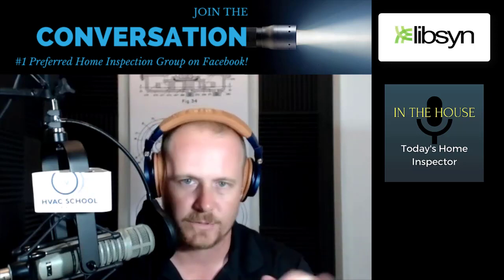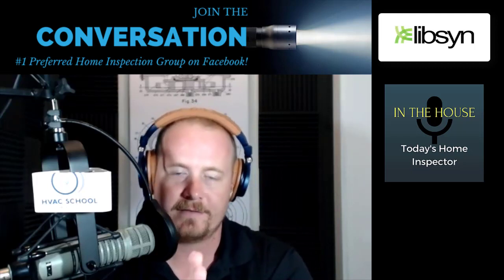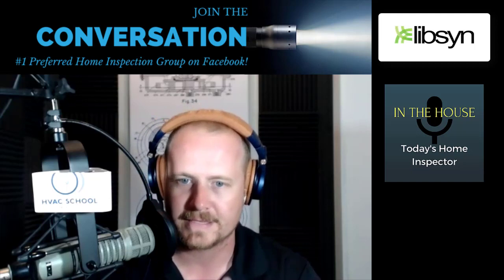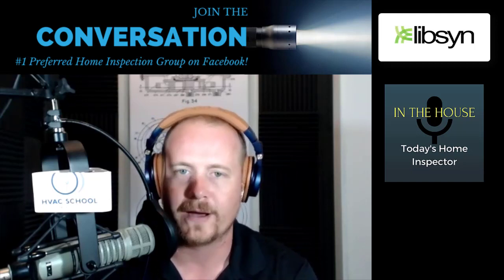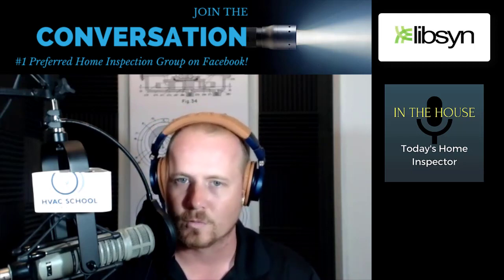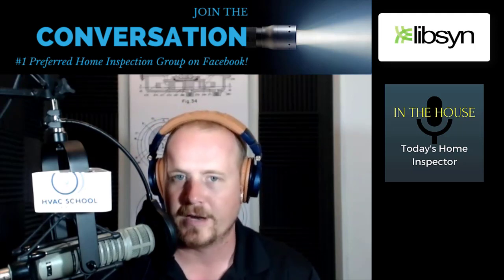20-degree Delta T is what you're looking for. And at 75 degrees Fahrenheit indoors with 50% relative humidity, that's pretty close. I mean, that's really close. But you have a lot of variation there. And that's where, when you go to a house and they've left it set on 75 or 76, and the relative humidity is normal, about what you would expect, then a 20-degree split is fine. But there is some variation there on either side.